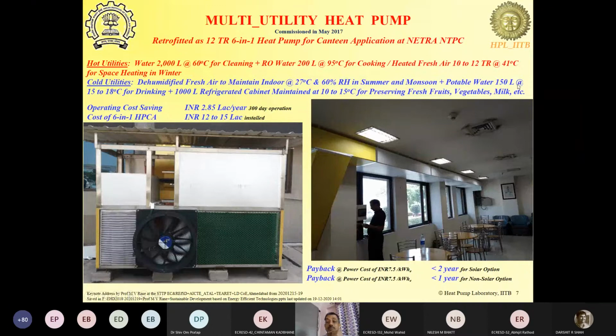150 liters per day at 15 to 18 degrees for drinking purposes. So anytime during the day, you can open the taps wherever they are located and get chilled water for drinking. This was filtered RO water, which was supplied into the unit, and then the unit would cool it from whatever the temperature, 30, 32, or even 37 degrees centigrade, down to 15 or 18 degrees centigrade, and that can be used for drinking.